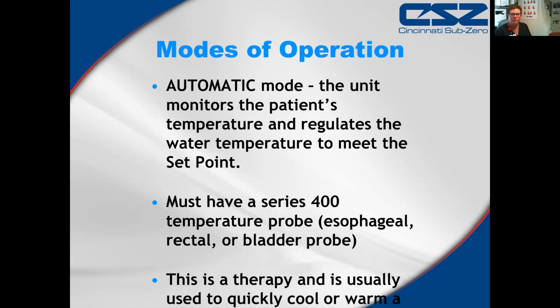Automatic mode is one that we use frequently, and this is the fastest way to get to target temperature. So the auto mode will allow you to cool or warm the patient as quickly as possible. But the reason why we don't maintain or leave the patient in automatic mode is because there is fear of overshoot, because it is very effective in getting that patient to target temperature. We use it to initiate. So within 4 hours, we like to have our patient at target temperature.